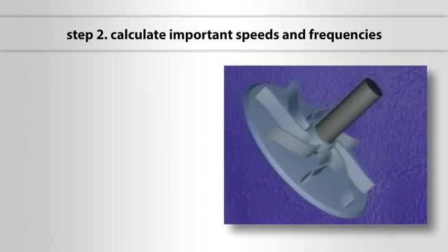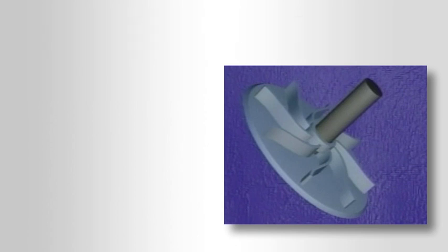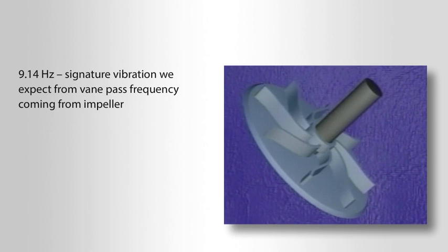Step 2: Calculate important speeds and frequencies. The one-times turning speed of the shaft is always the first speed you'll want to determine. In this case, the shaft is turning at 9.14 Hz.